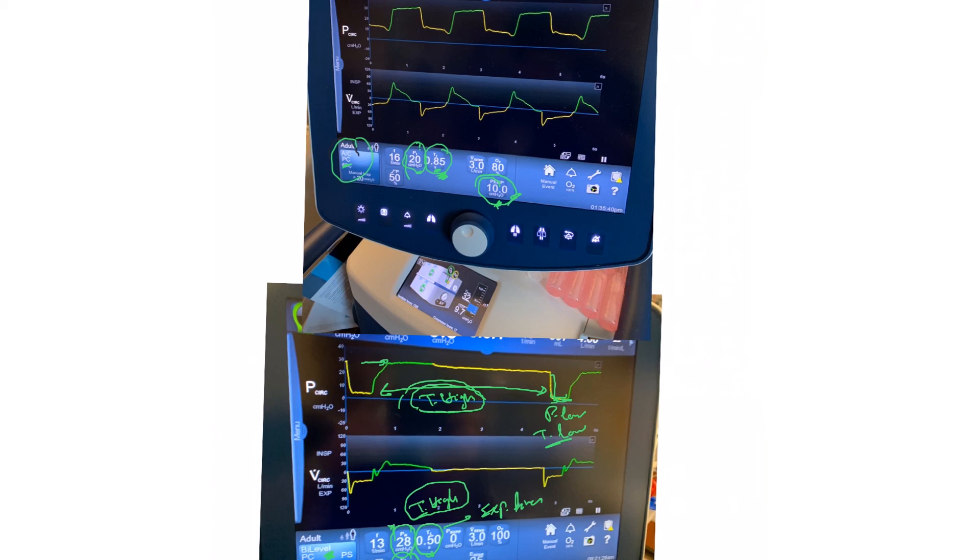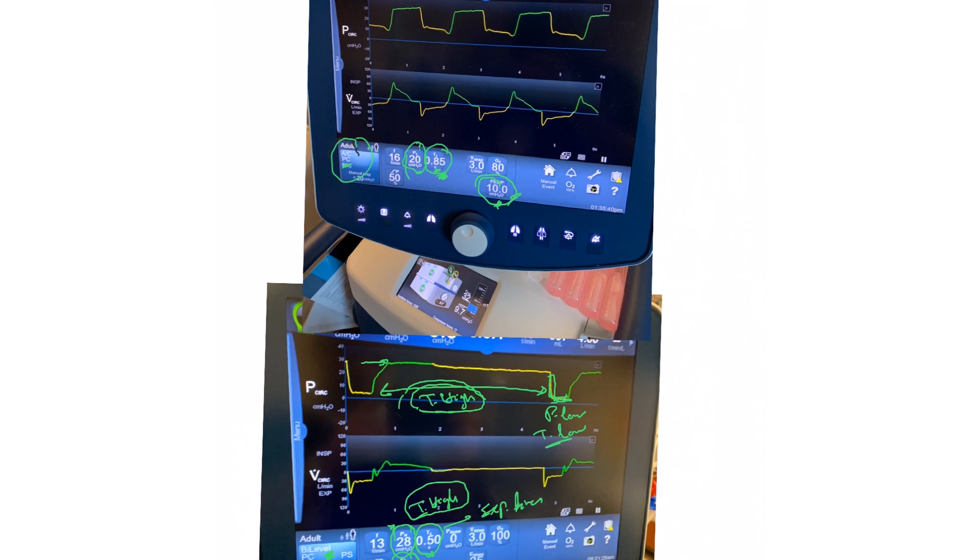Then we release that. We go to a lower pressure called P low, which correlates to PEEP on the traditional pressure control mode, for a specific period of time called T low, which correlates to expiratory time on a traditional pressure control mode. Then the cycle repeats itself. Let's continue next video.